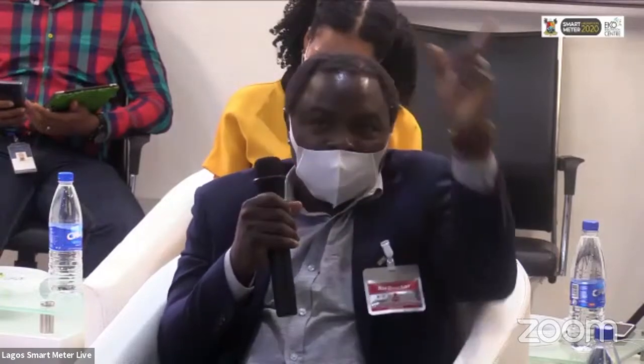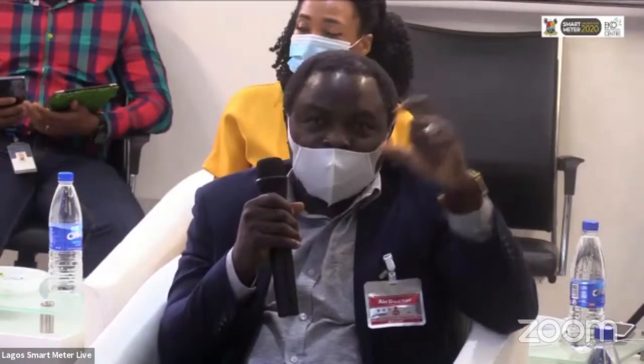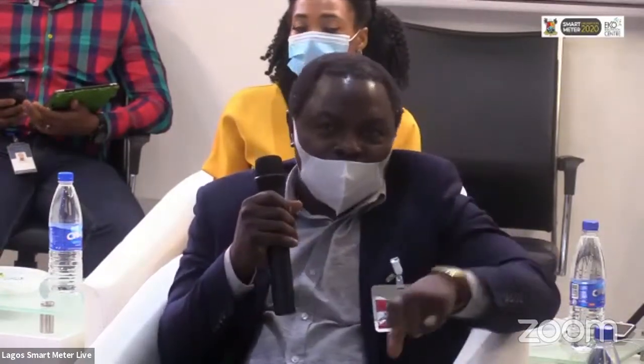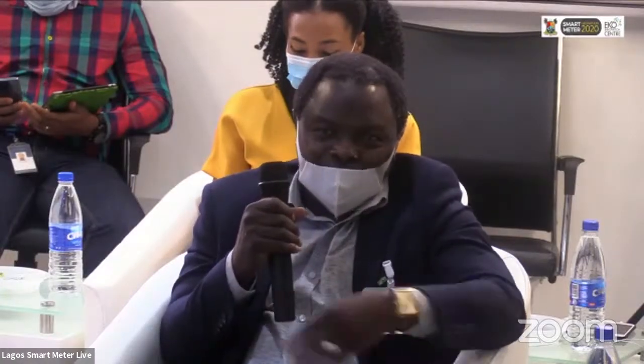So in considering cost, these are things you have to factor in. Most of these meters might not even pass class 3 in terms of accuracy. But in the grid we use class 0.2 because of transmission losses and the sensitivity of the value of energy being conveyed. In the house we use class 1 or class 2, as the case may be. These are part of the cost considerations when designing.